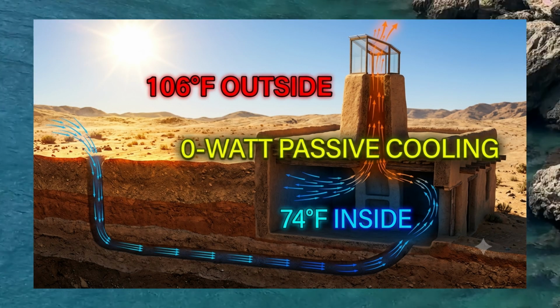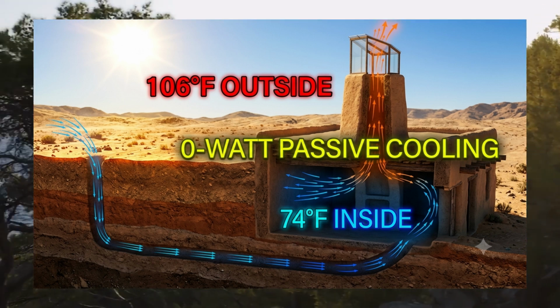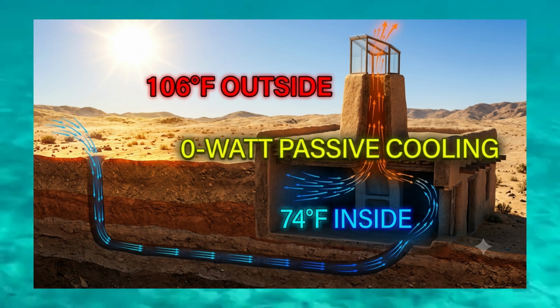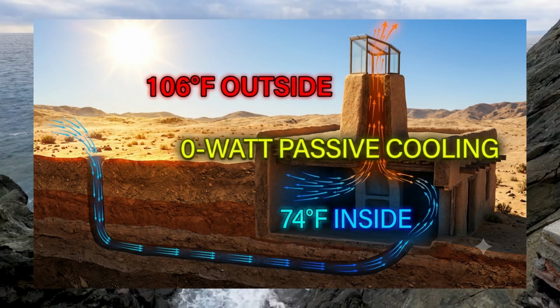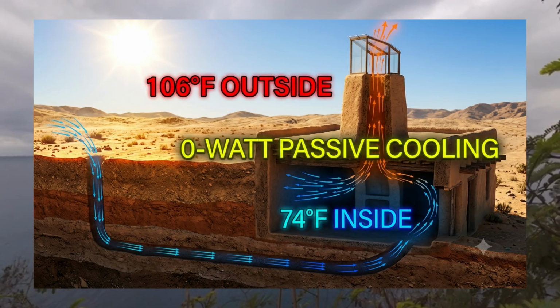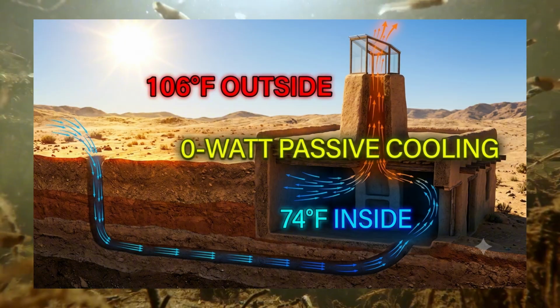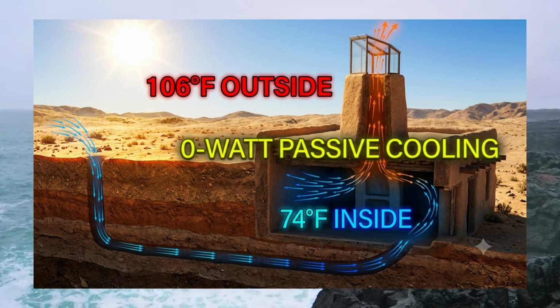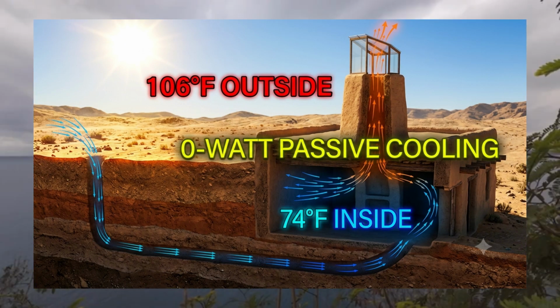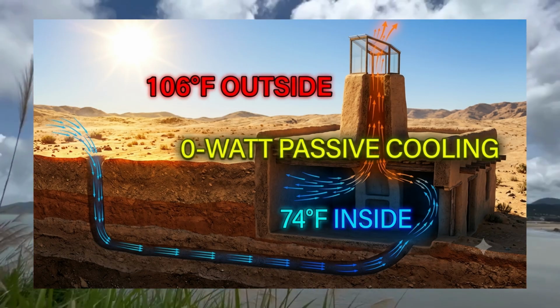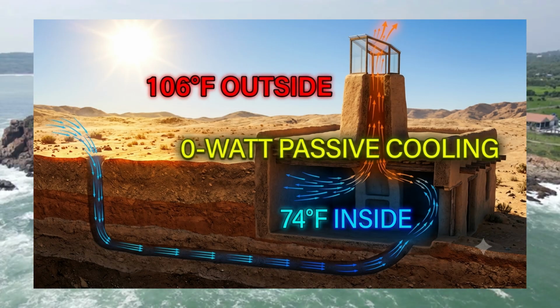In these trenches, we lay smooth, heavy-walled conduits. It is a common mistake in modern off-grid builds to use cheap, corrugated agricultural pipe for this purpose, but that is a recipe for system failure. The interior ridges of corrugated pipe create immense boundary layer friction, slowing the passive movement of air to a crawl.